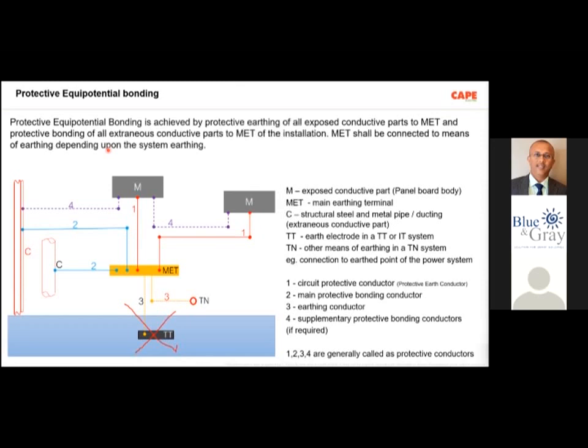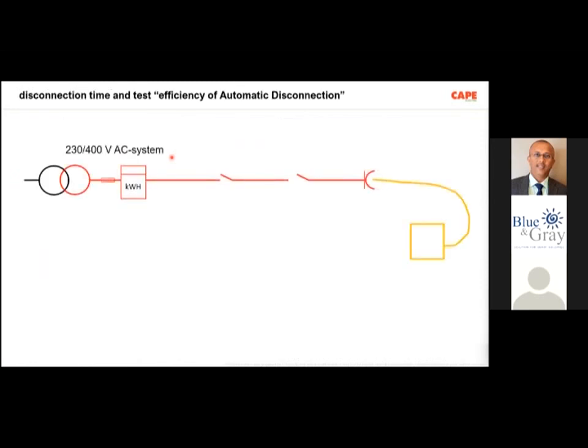The protective equipotential bonding is achieved by protective earthing of all exposed conductive parts to the MET, and protective bonding of all extraneous conductive parts to the MET of the installation. The MET shall be connected to the means of earthing depending upon the system earthing, sometimes to the earth electrode or sometimes to the source of the transformer.